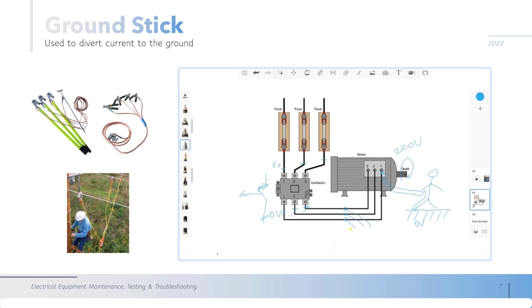and the ground protective equipment is with a shunt or common point and another end you connect to the ground. In this situation, when this contactor fails and closes, the voltage will be applied here in this line, but the current will not flow to the motor or to you, because the motor has a resistance different from 0 and you also have a big resistance different from 0. So the current will prefer to flow directly to ground in the easiest path without resistance, because resistance creates opposition to the passage of electrons.